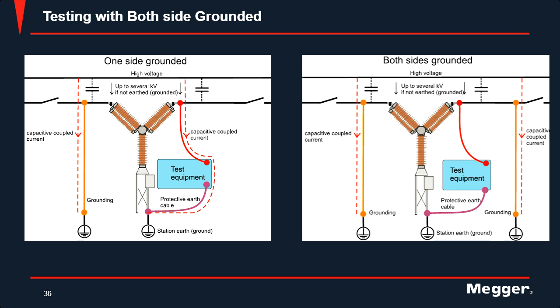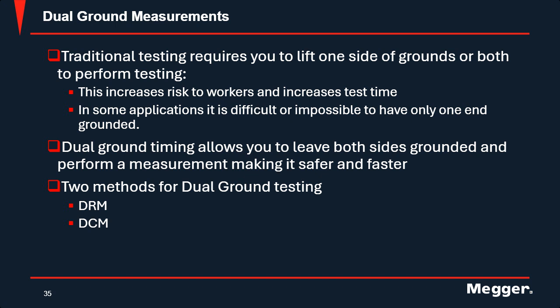So dual grounding allows you to have both grounds attached at the same time and do your timing test. Now, like I said, traditional testing requires you to lift one side or both to perform the test. There's an increased risk to the workers, and it increases your time. Especially for utilities, every time you have to lift a ground and reground, you have to talk to operations. There might be a delay in that and it can add time to your testing.